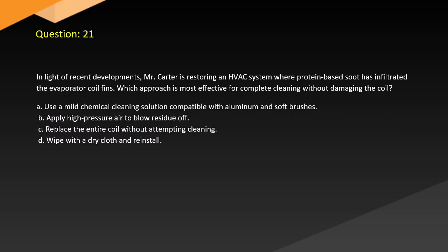Question 21. In light of recent developments, Mr. Carter is restoring an HVAC system where protein-based soot has infiltrated the evaporator coil fins. Which approach is most effective for complete cleaning without damaging the coil? A. Use a mild chemical cleaning solution compatible with aluminum and soft brushes. B. Apply high-pressure air to blow residue off. C. Replace the entire coil without attempting cleaning. D. Wipe with a dry cloth and reinstall.